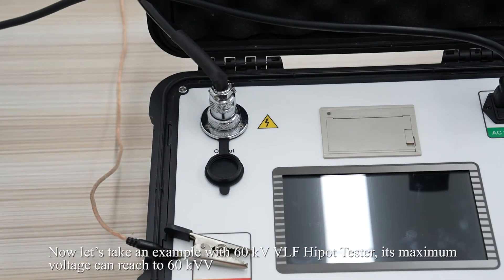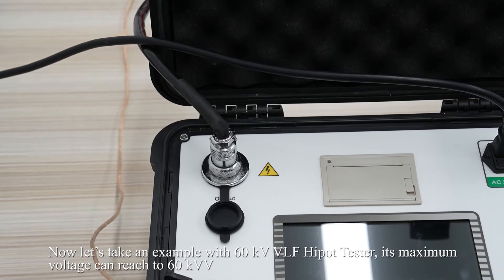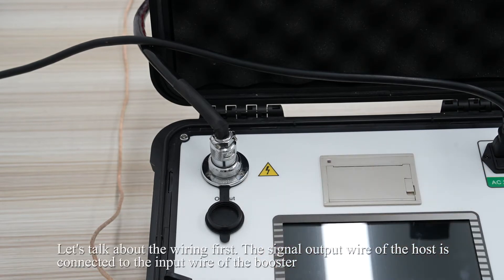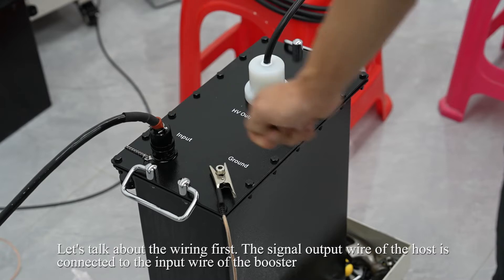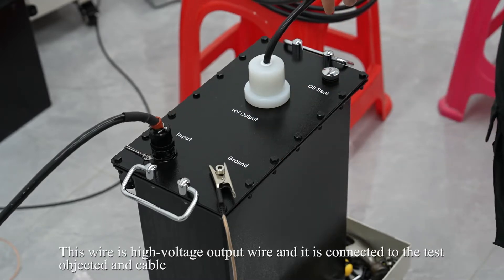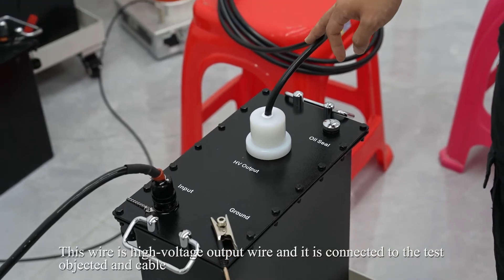Now let's take an example with 60KV ultra-low-frequency hipot tester. Its maximum voltage can reach 60KV. Let's talk about the wiring first. The signal output wire of the host is connected to the input wire of the booster. This wire is high-voltage output wire and is connected to the test object and our cable.